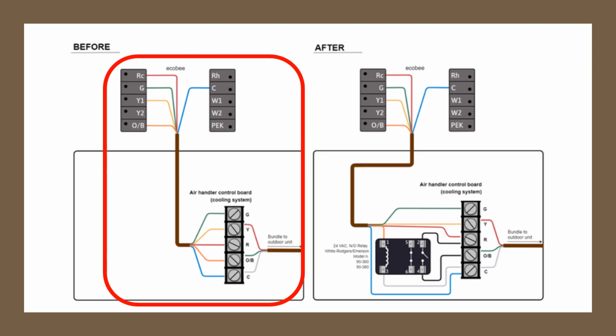So to resolve this issue, an isolation relay was used to isolate the OB terminal from the thermostat, so that when the thermostat called, it would energize the isolation relay, closing the contact to make the circuit to the O and B terminal, thus isolating the thermostat from the system and resolving the overheat situation.